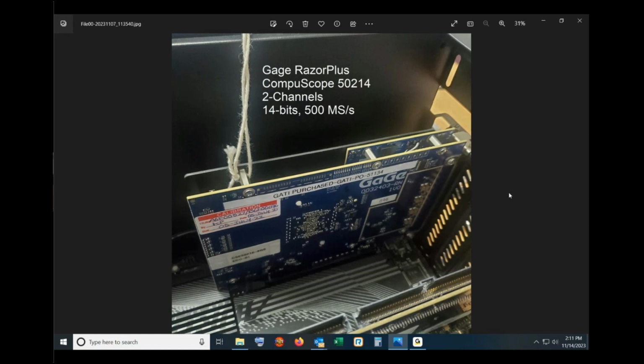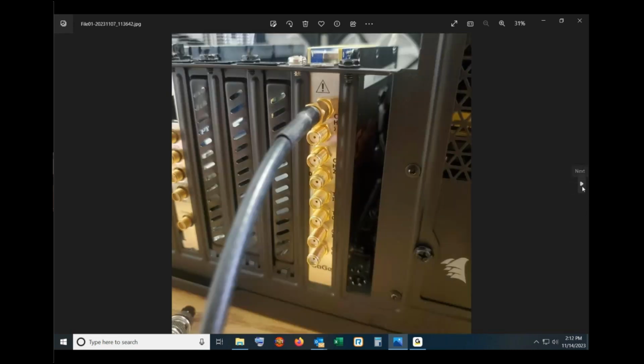So I'll be presenting some measurements on a Gage RazorPlus, and most of them will be within the context of ultrasonics measurements. I did a number of measurements here in our Gage lab with a bunch of instruments, really highlighting the Gage RazorPlus CompuScope 50214, which is a 2-channel, 14-bit, 500 megasample per second digitizer. You can see it here installed in a PC. It's a half-length card, so there's plenty of space there. From the back end, it's got SMA input connectors. You can see a signal connected to channel 1, and then the auxiliary connections at the bottom: trigger in and out, clock in and out, some of which we'll be discussing.